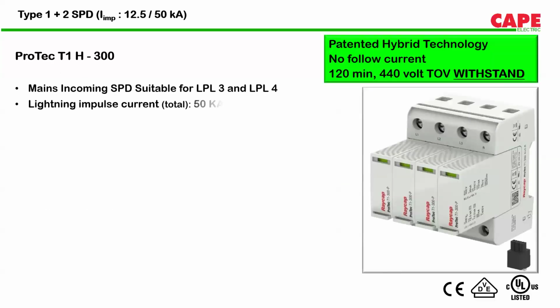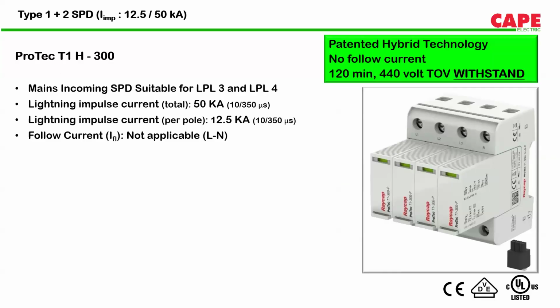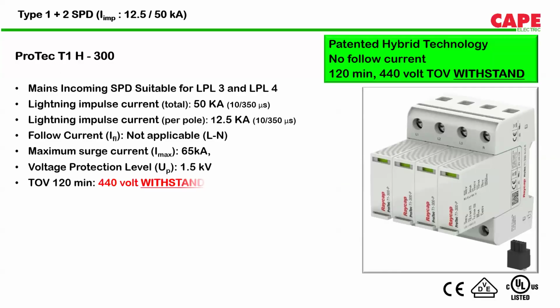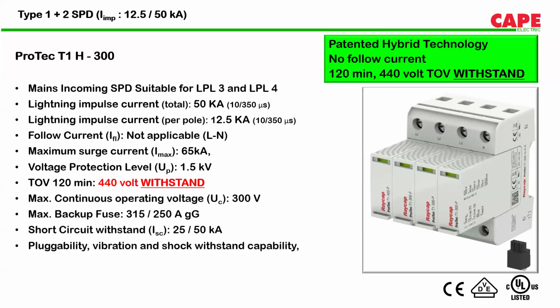Now these are the second series of SPDs, called the T1H series. It can be Protec or TSD. These are similar to T1HS SPDs. These are TOV withstand SPDs, but have an impulse current rating of 12.5 kA line to neutral and 50 kA neutral to earth. Now there is one more advantage these SPDs have: they are leakage current free SPDs.